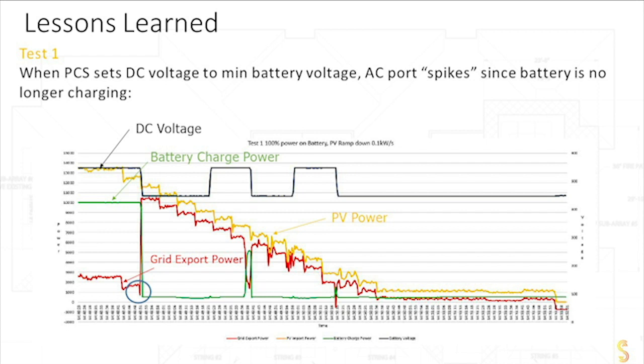close to zero, and it hits a minimum threshold, at which point the inverter says, uh-oh, you're about to import energy from the grid because your battery is charging and your export out into the grid is going down. So you're about to import energy from the grid. You're getting dangerously close to zero. I'm switching you off. And at the same time, as you get dangerously close to zero, as the red line gets close to zero, now the battery voltage turns off, or it gets set below the operating window. So it was about 500 volts before, now it's dropped down to something less than that.